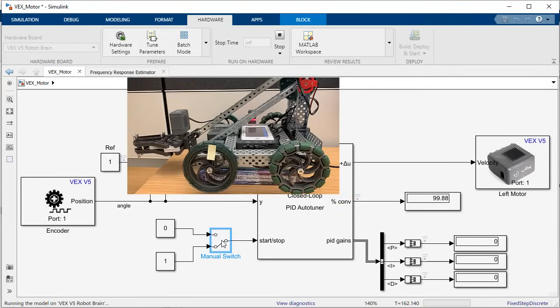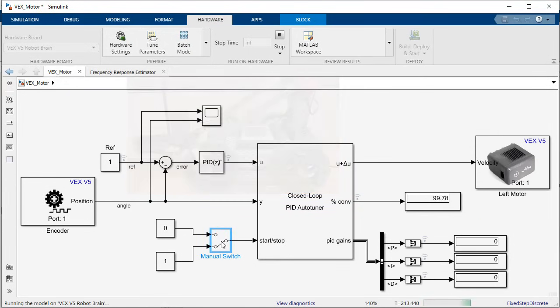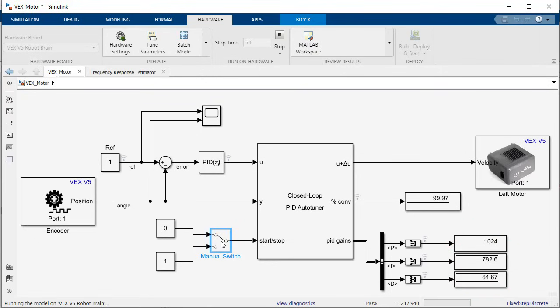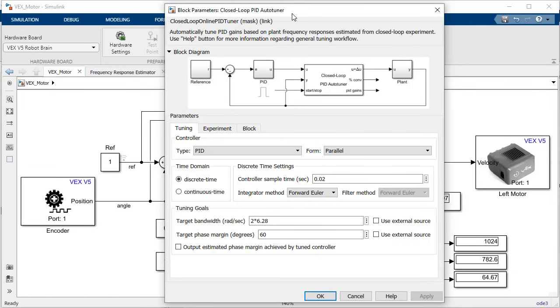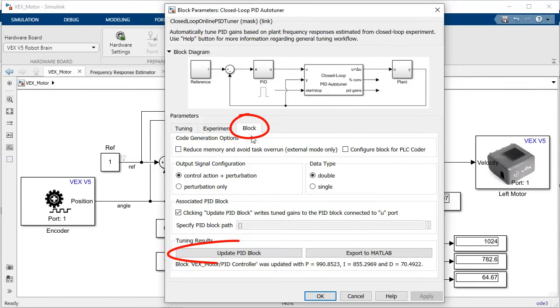After the test has been enabled and the convergence is close to 100%, you can stop the test and get the new PID gains. It is also possible to update the gains from your PID block directly from the block tab on the auto tuner block parameters. In this case although we have some overshoot we improved our response time and eliminated the steady state error.